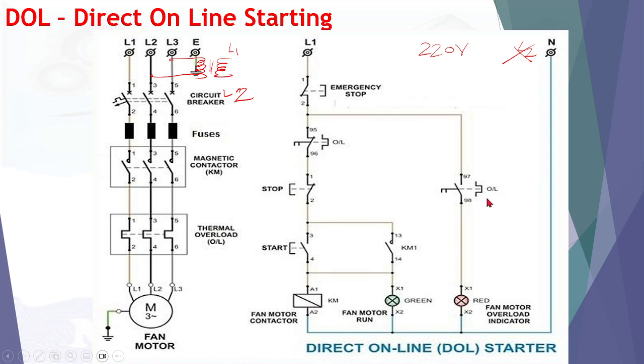This is the basic idea of the DOL starter — there is no voltage reduction, only direct power supply with protection devices. When you want to stop, simply press the stop button; power is cut from the KM1 contactor and the latching contact opens, stopping the motor. The main disadvantage is it draws high starting current, though the advantage is high starting torque. For large motors, DOL is not suitable because it heavily affects voltage dip and power factor.